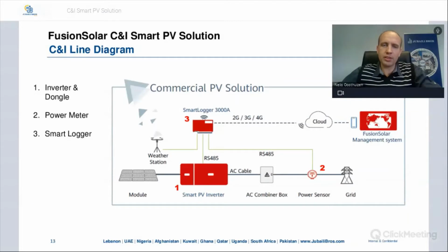So it's Huawei inverters, C&I range starting at 20 KTL, going all the way up to 100 KTL. Power meters: the power meters they've got available are for both residential and C&I. A note to remember is that the power sensors for C&I are only for the smaller scale commercial industrial. As soon as you go to more than 250 kilowatt on a commercial industrial, you would require a third-party power meter. But again, you can get that power meter from Jubaili Bros, so we will assist you on that one.